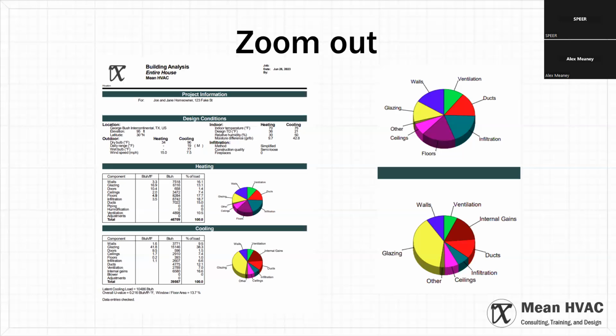Yeah, I agree with that. And I guess the issue I was running into when I was doing energy inspections was the complaint and issue was sweating ductwork or raining ductwork. So instead of recalculating the load calculations, they just stubbed out a supply and stubbed out a return and said, you're good, which it solved the issue, but I think it clouded the load calculation for the rest of the house.